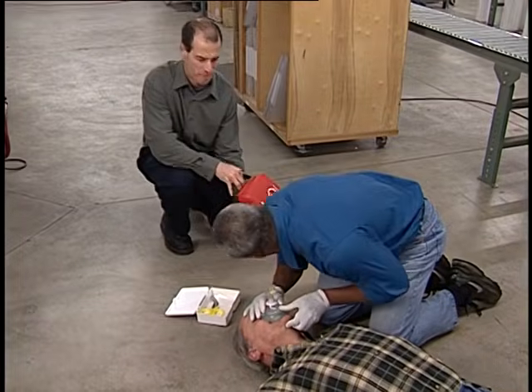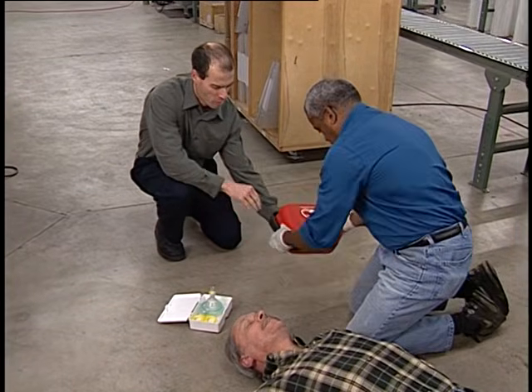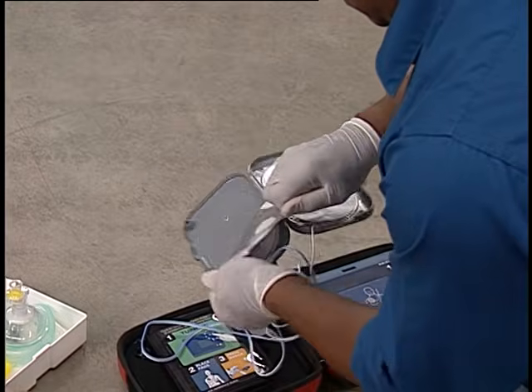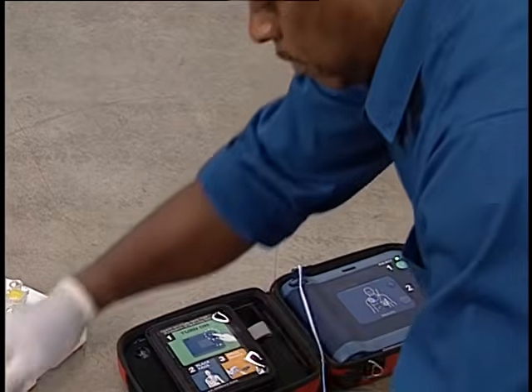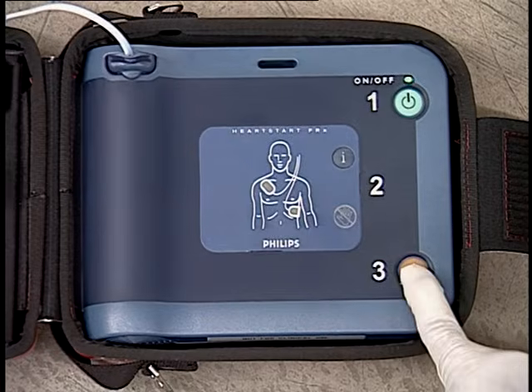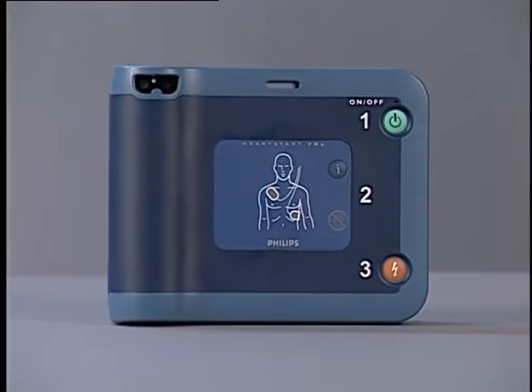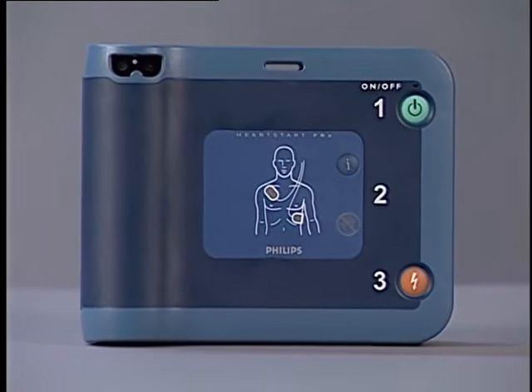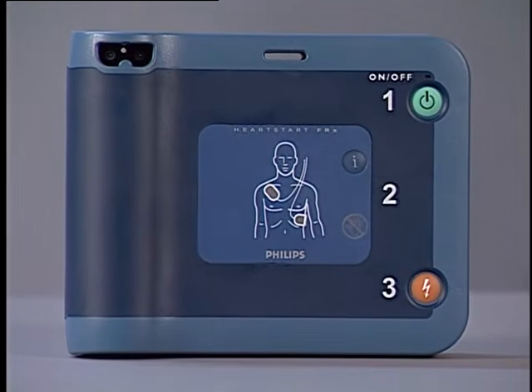Data management is simple with the HeartStart FRx defibrillator. It automatically stores in internal memory detailed data from its last use, including the first 15 minutes of ECG. As long as the battery is not removed, ECG data will be retained in the defibrillator's internal memory for 30 days. Additional data is stored for up to 7 years.